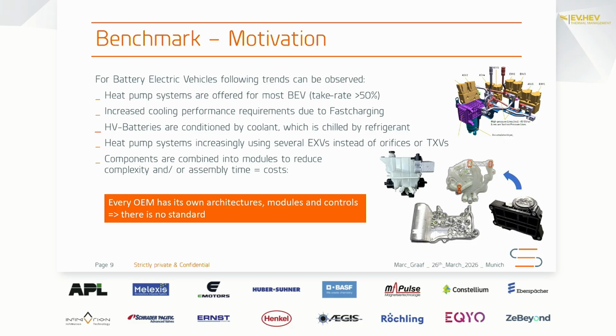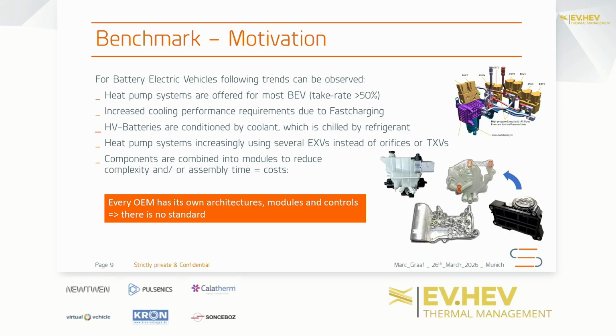Nowadays we see that there are one or more externally controlled expansion valves in such a system, so that you're also able to control the refrigerant flow and the temperature levels in each heat exchanger the way you would like to have it, and to have it optimal, so that you're able to operate your system also at minus ambient temperatures. And another trend, of course, is the modules that are being built to save cost, to put together some components in modules or subsystems.